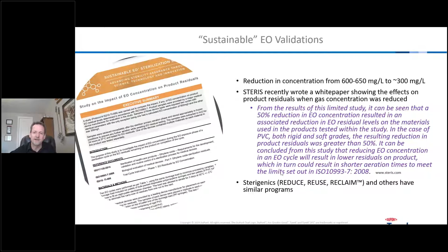So what are companies doing? Again, the FDA came in and they're looking at what you can do to your current process to help with this issue. Ethylene oxide is a gas. It has to penetrate into the product, and then it has to be able to come out of the product after the cycle. So anything that can help penetration and enhance aeration is going to be critical.